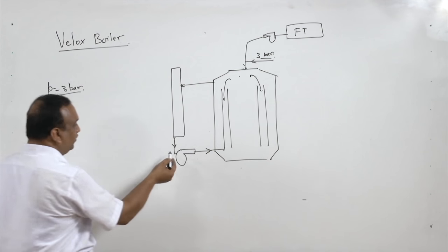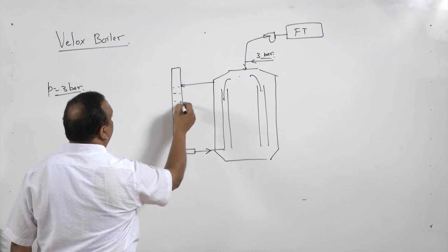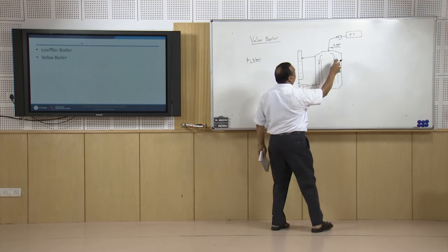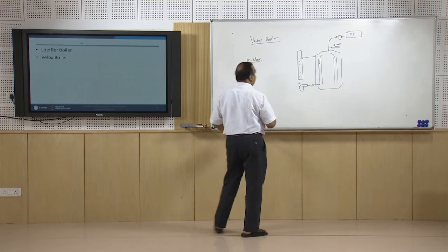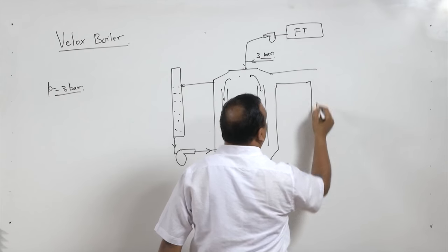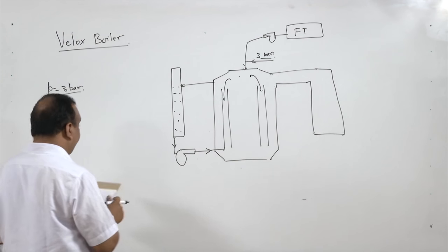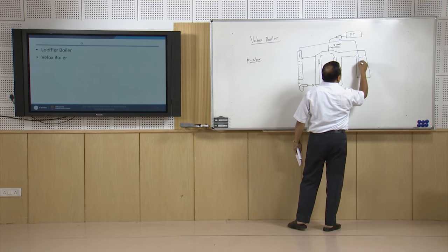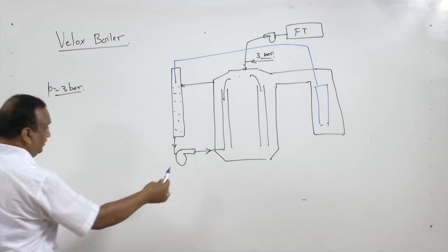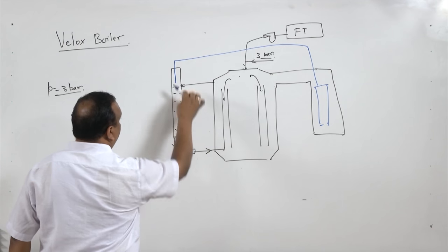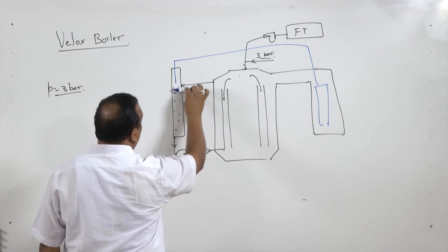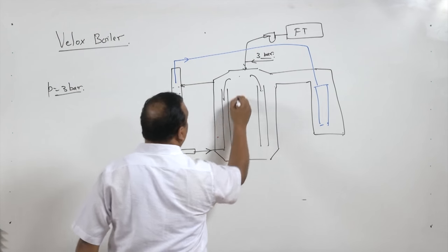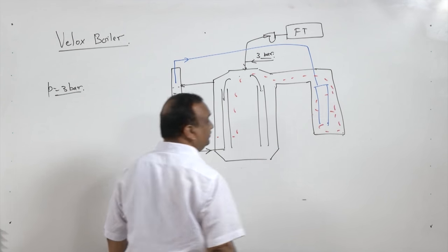The pump draws water from the steam separator, and generated steam goes back to the steam separator — it is a closed loop. Every high pressure boiler must have a superheater. Flue gases from this chamber go to the superheater. The saturated steam collected in the steam separator goes to the superheater, where superheating takes place. The area around the superheater is filled with the flue gases.